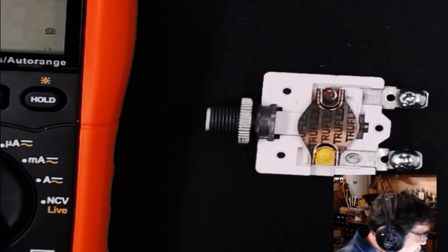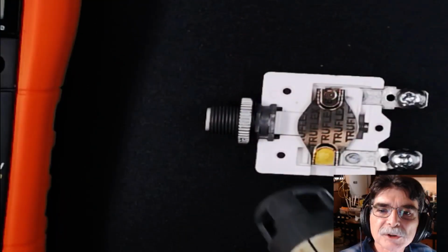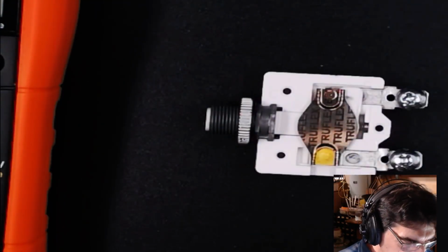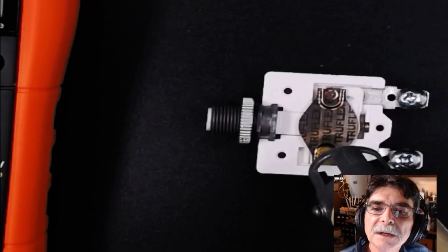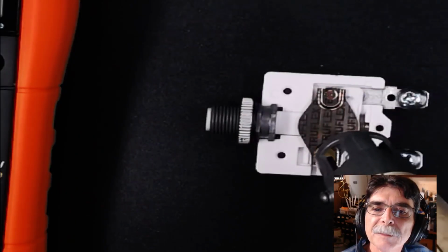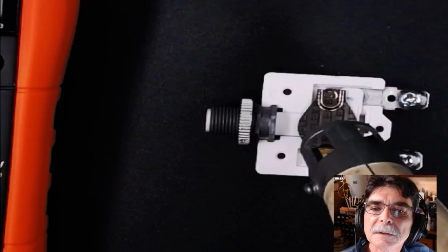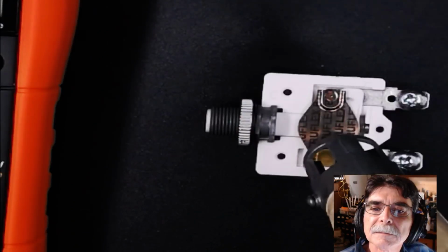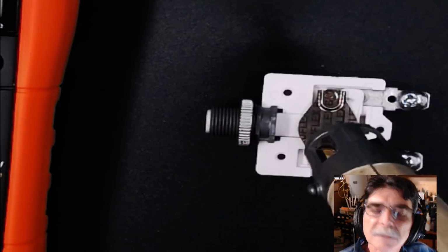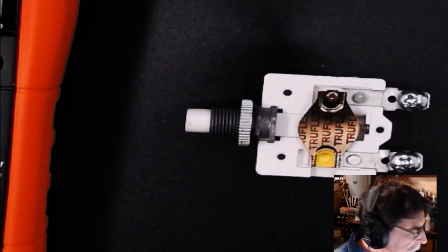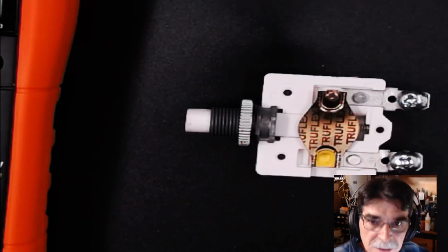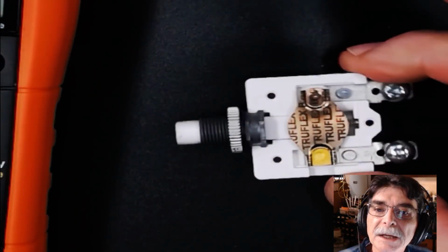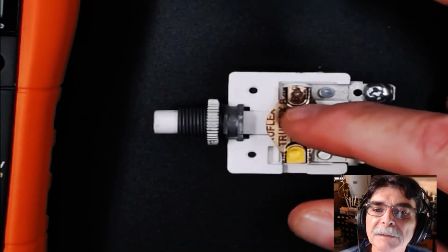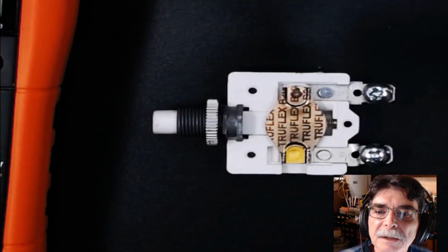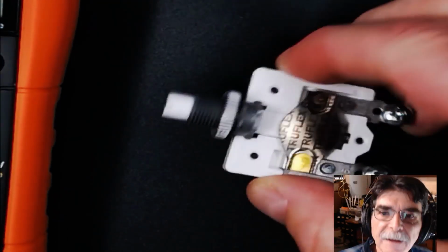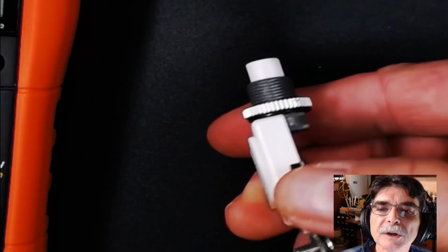Here's what we're going to do. I'm going to take my heat gun and show you what happens with the bimetallic element when it heats up. So I'm heating the bimetallic element up with my heat gun. Here we go. So you can see that it's heat related. In other words, when I heated up the circuit breaker, the bimetallic element bent up and allowed the spring to push the plunger out, and now we have an open circuit breaker.